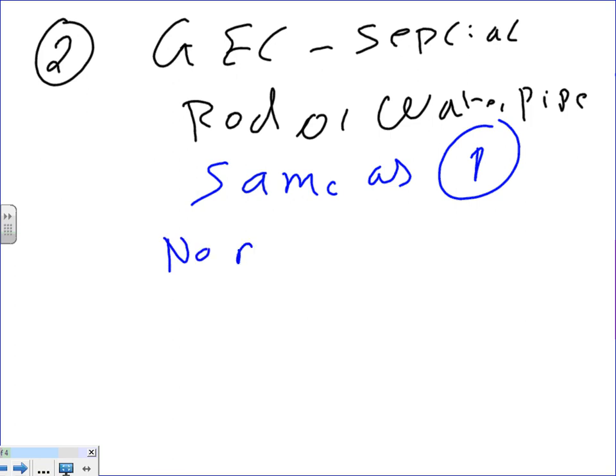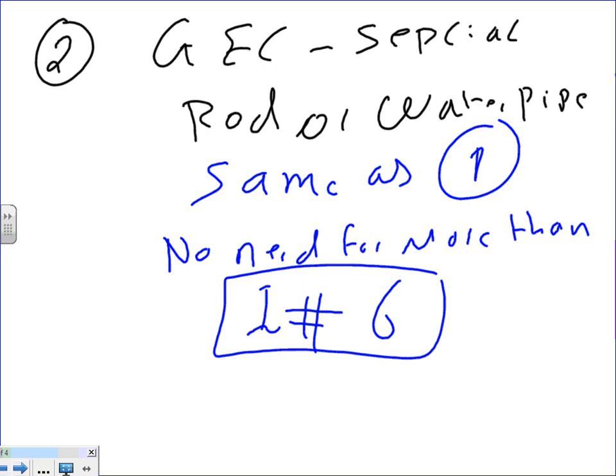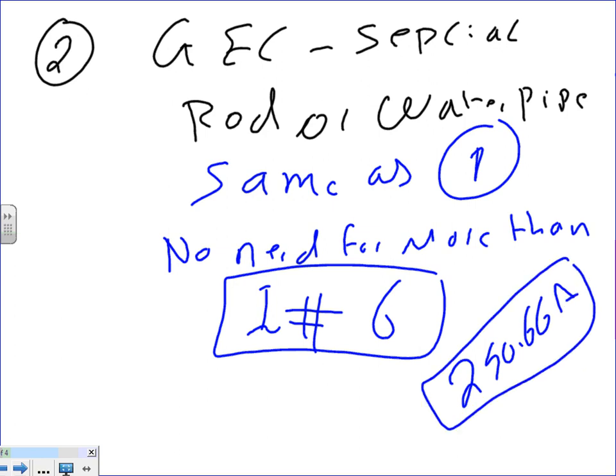You do the same calculation as in 1, but you really don't need to go higher than number 6. If you don't believe me, go to the code, right under 250.66. It will tell you if you're tying it to a rod or a pipe, you don't need to go higher than number 6. Special condition, rod or water pipe, 250.66(A). Any question, guys, about number 2?